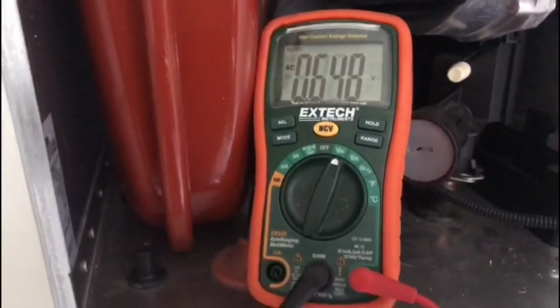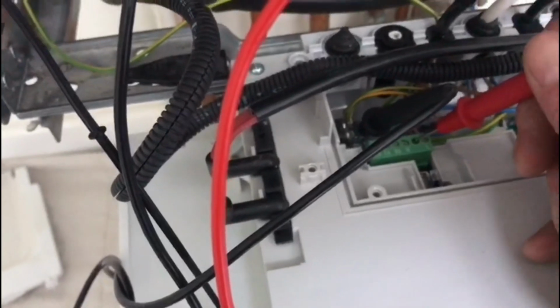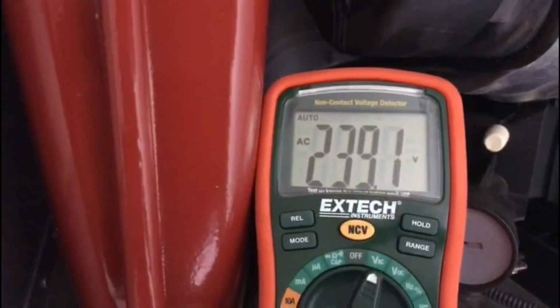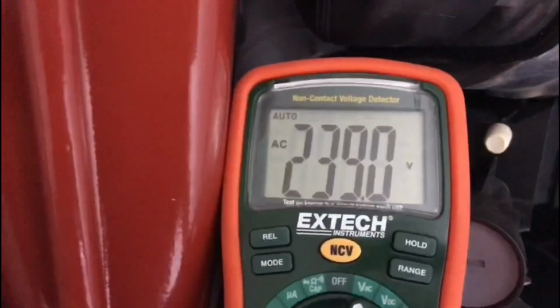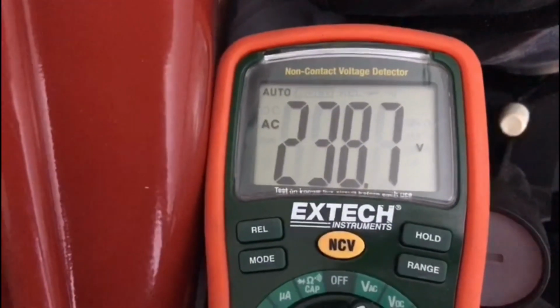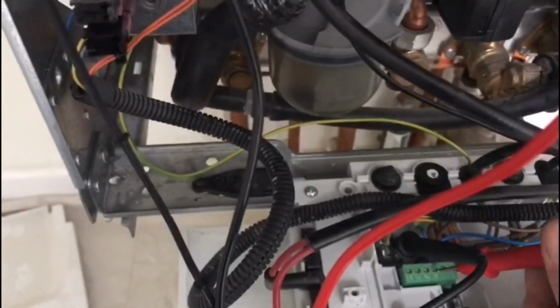So the first test you've got to do is test between your live and earth. It's already on my earth pin, so you test live to earth. Should be getting a reading of 240 volts around about there, or depending. Got 238 volts there.